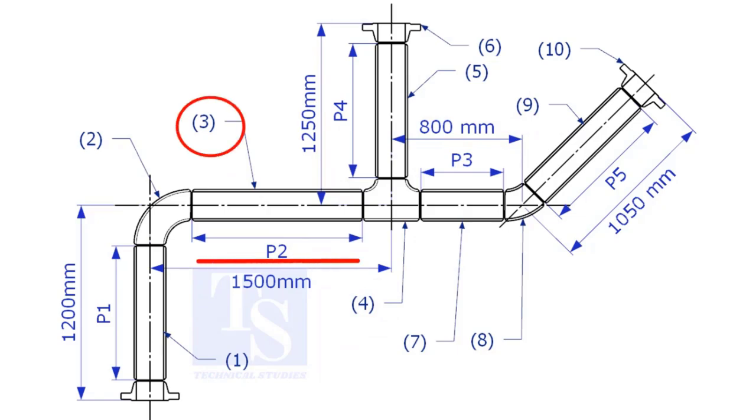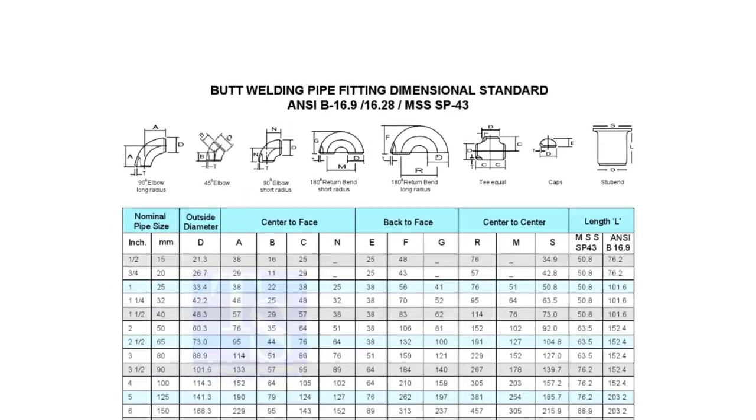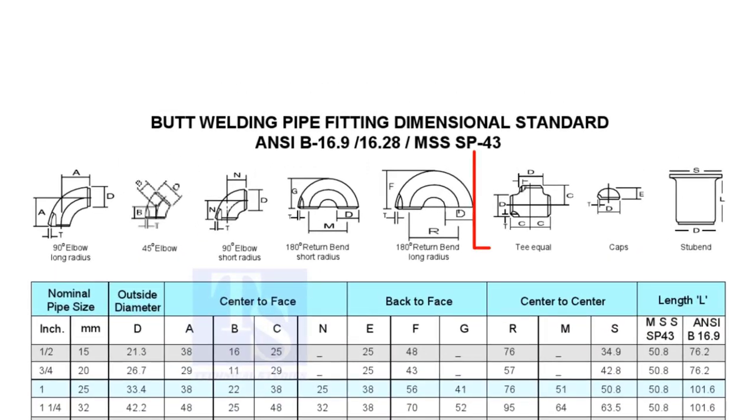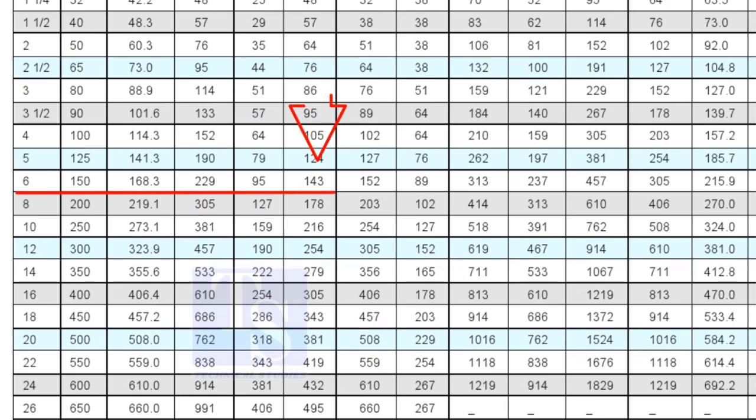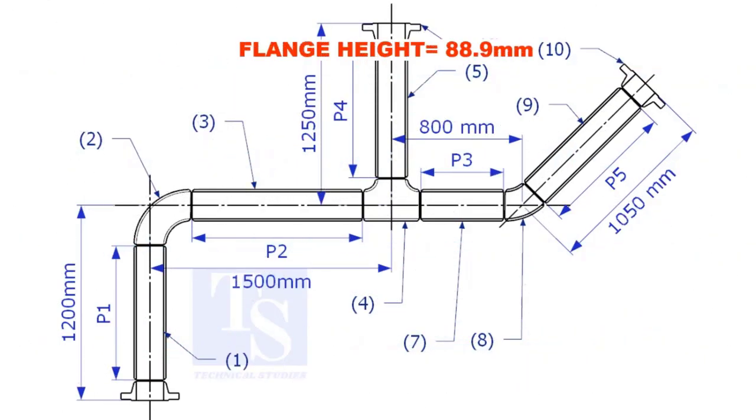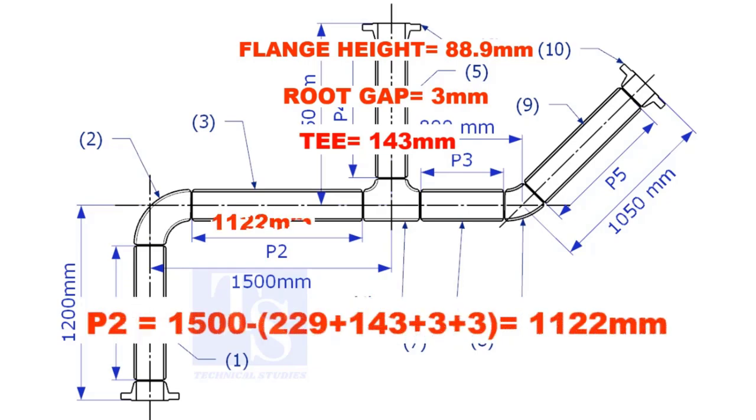Let us calculate the length of item number 3. We already know the takeoff length of the 6 inch long radius elbow. Now, check the chart for the takeoff length of the equal T. It is 143mm. The length of item number 3 is 1122mm.